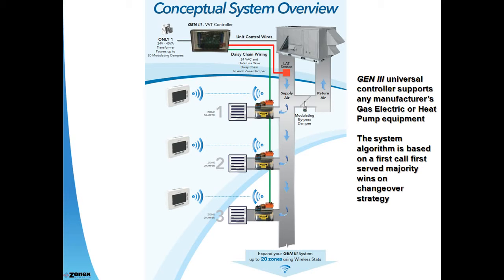System wiring is very easy. From the GenIII controller, the installer pulls 24 volts of power and an unshielded 2-wire communications loop, daisy chained from damper to damper with no home runs. All dampers are fully modulating and they support up to 1.75 inches of static. A communicating damper board resides on each damper, enabling wireless communication between the zone thermostats and each damper. The system also includes a fully modulating bypass with integrated static pressure control.